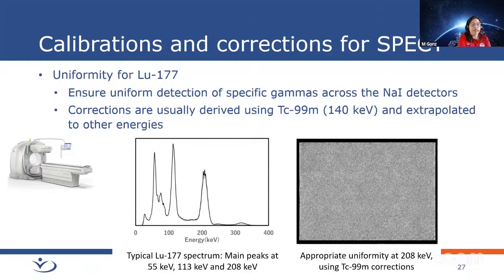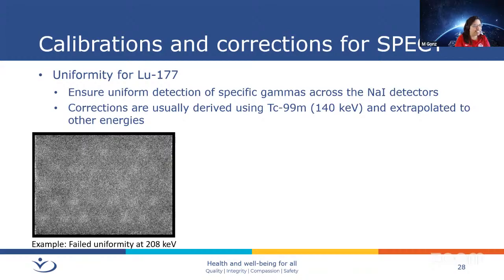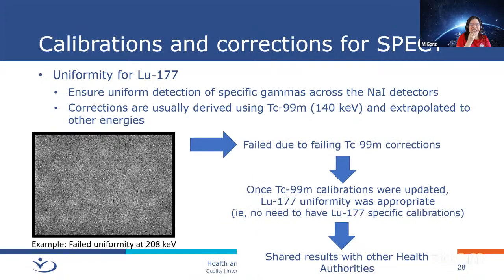And we did find some where it was not okay. This is one camera where the uniformity check failed at 208 keV. So in this case, something was going on with this camera that it was not responding appropriately. What we figured out in the end is that it was failing because the technetium corrections and calibrations were failing already. The camera had been drifting from calibration, and technetium had started to drift already, but they hadn't noticed it because it wasn't as bad. But once you look at 208 keV, you can tell that the camera is starting to go off from the calibrations. Once we recalibrated this camera with technetium, the lutetium uniformity was acceptable too.